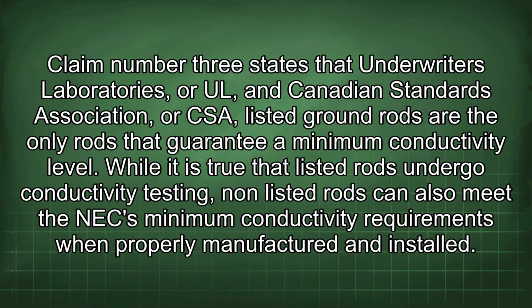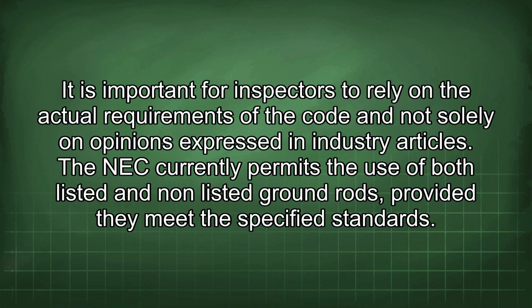Claim number 3 states that Underwriters Laboratories, UL, and Canadian Standards Association, or CSA, listed ground rods are the only rods that guarantee a minimum conductivity level. While it is true that listed rods undergo conductivity testing, non-listed rods can also meet the NEC minimum conductivity requirements when properly manufactured and installed.